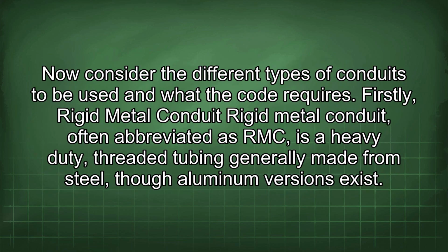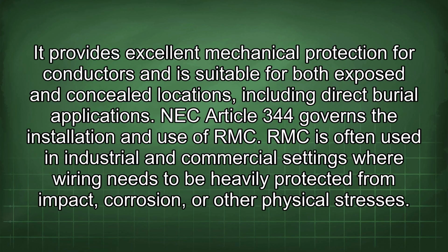Now consider the different types of conduits to be used and what the code requires. Firstly, rigid metal conduit. Rigid metal conduit, often abbreviated as RMC, is a heavy-duty, threaded tubing generally made from steel, though aluminum versions exist. It provides excellent mechanical protection for conductors and is suitable for both exposed and concealed locations, including direct burial applications. NEC Article 344 governs the installation and use of RMC.